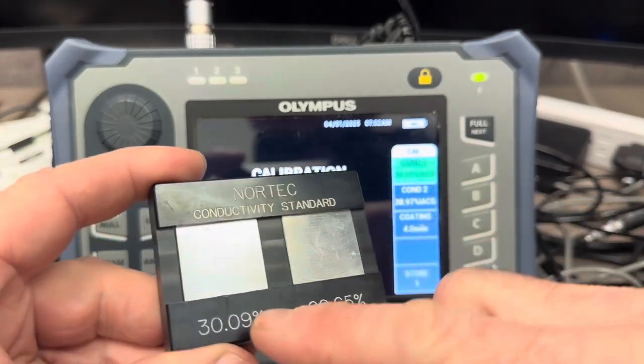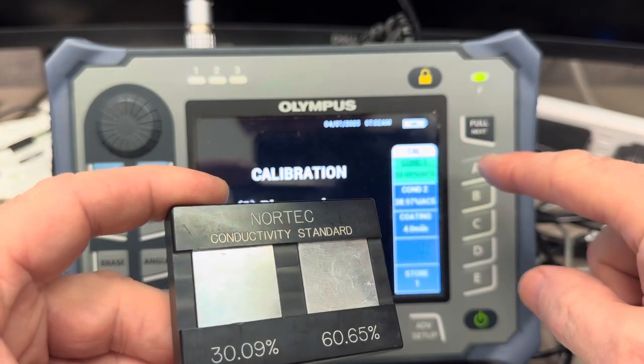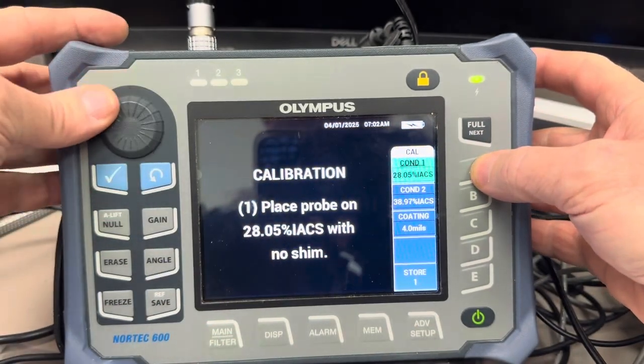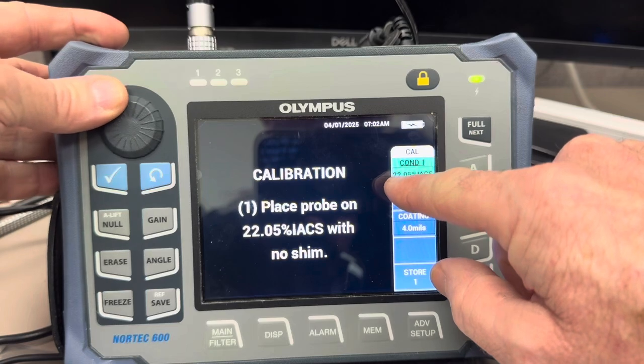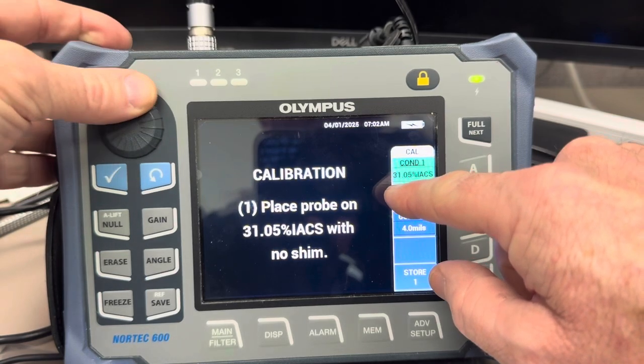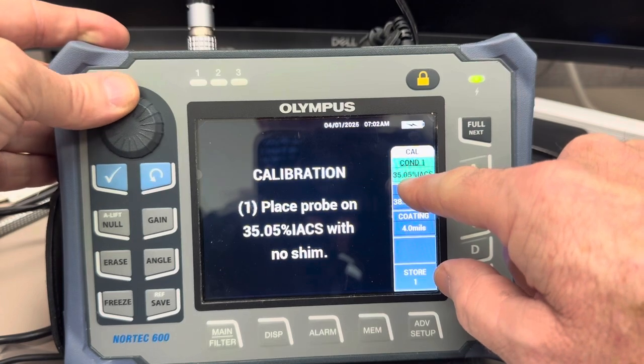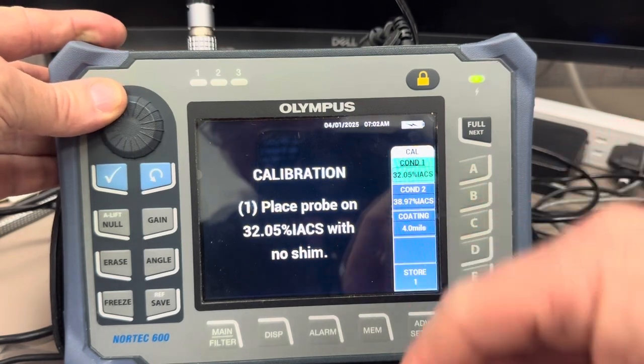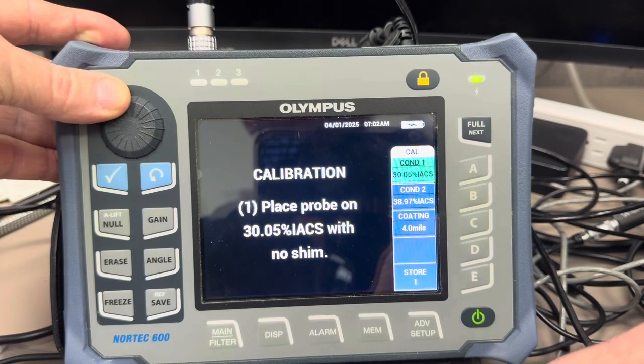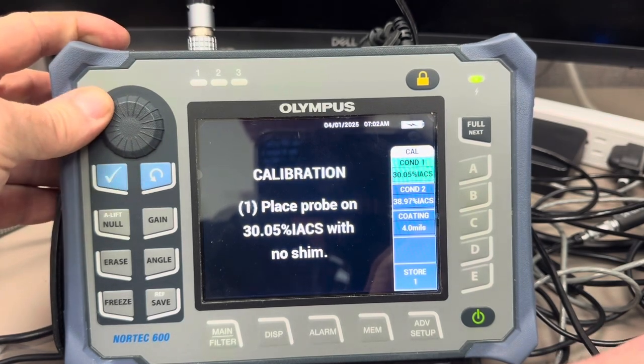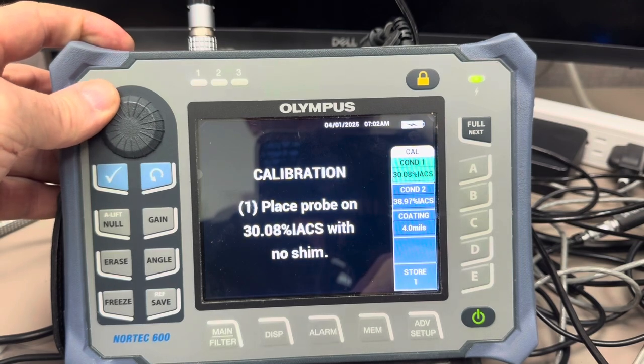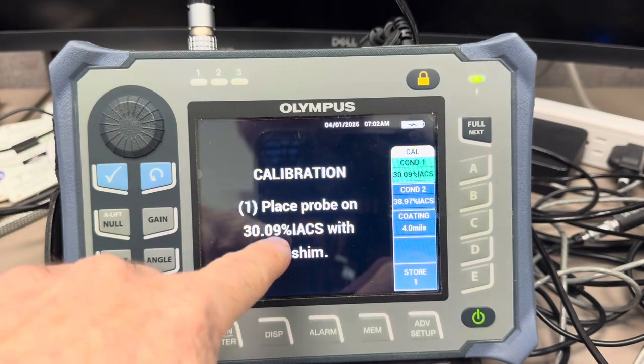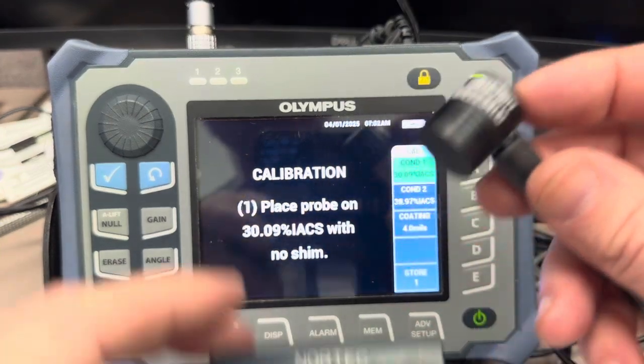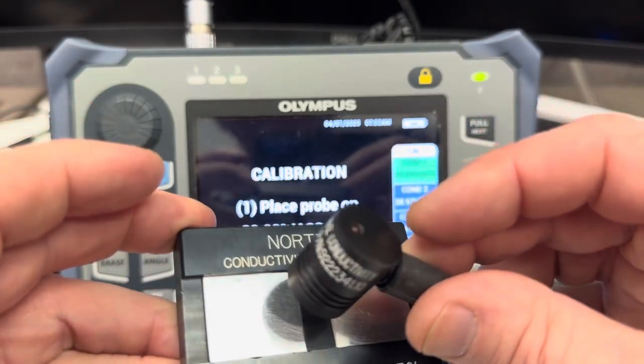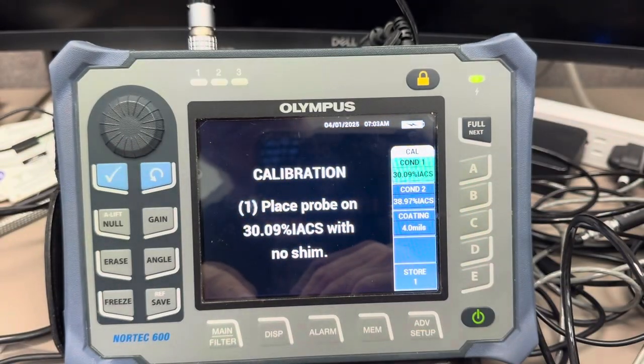Well, I don't have 30.05, I have 30.09. So you have to adjust it in the instrument. So if I try to adjust it, you notice how it's adjusting the tens and I want to adjust the hundredths here. So what you have to do is first get it close. So we'll set it to 30, and then to adjust it fine, you have to hit the check mark. And now we can take it up to 30.09. All right, and it adjusted it here. So I'm just going to take my conductivity probe, and I'm going to place it on the 30.09 IACS with no shim. And I'm just going to hit store point 1.